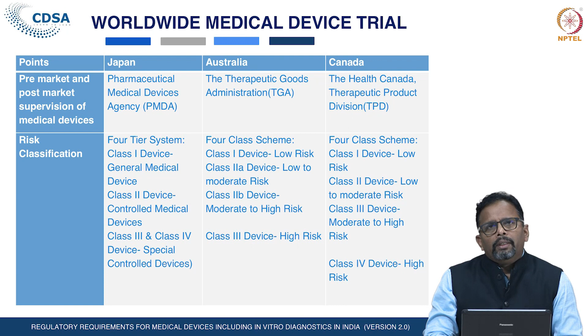They have classified the medical devices based on the risk. In Japan, the medical devices have been classified into class 1, class 2, class 3 and class 4, wherein class 1 is the low risk devices and class 4 is the high risk devices requiring special control. In Australia, the classification system is in line with the European system, where there are class 1, class 2A, class 2B and class 3; class 1 is the low risk and class 3 is the high risk. In Canada, the classification scheme is again class 1, class 2, class 3 and class 4 devices, where class 1 is the low risk devices and class 4 is the high risk devices. And for the low risk devices, as already discussed, there is no requirement of clinical investigation.